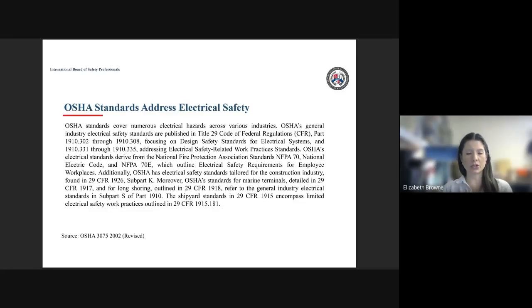The OSHA standards are derived from the National Fire Protection Association standards found in NFPA 70 in terms of their electrical standards. We'll also talk about the NFPA 70E standards that address arc flash safety. And then we will also reference the National Electrical Code that OSHA utilizes for their electrical safety standards.